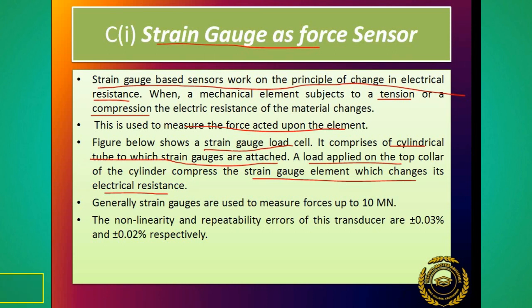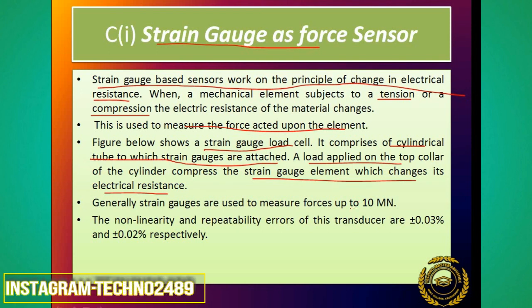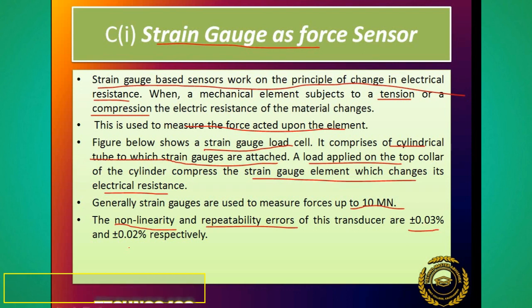Generally strain gauges are used to measure forces up to a specified range. There are non-linearity errors and repeatability errors - as I already explained in performance terminology. The non-linearity error for this transducer is plus minus 0.03, and the repeatability error is plus minus 0.02 in this type of force sensor.